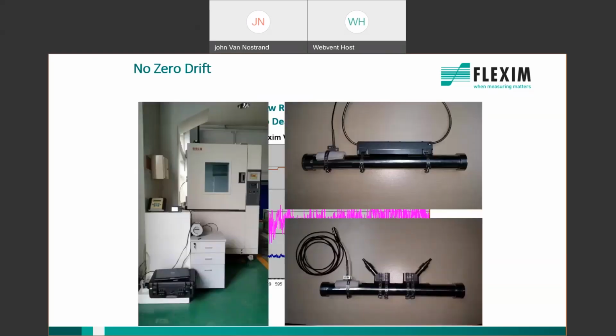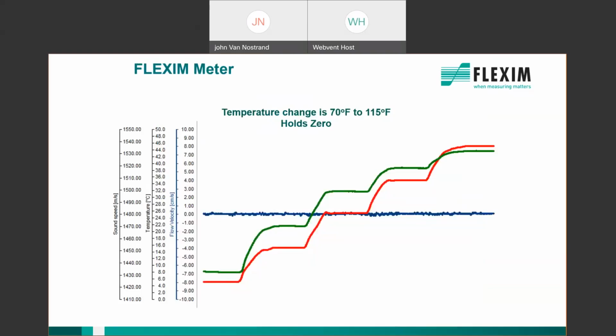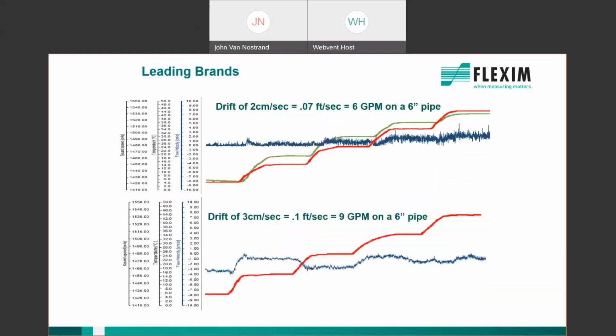So then we took it a step further and thought, let's put it in a controlled environment. Let's put it in an oven and control the temperature to see if that zero fluctuation makes a difference. Here's what we learned. This is the FLEXIM meter, and what we're seeing here is the blue line shown as our zero point, where the green and the red are two major competitors. You can see over time that the meters drift while the FLEXIM meter remains nice and solid. And if you take a look at what that drift translates to, it shows 0.1 feet per second on one meter and 0.07 on another. And that on a 6-inch pipe is either 9 or 6 gallons per minute, respectively. So it's quite significant, especially over time.